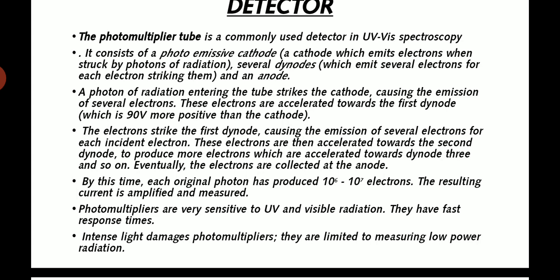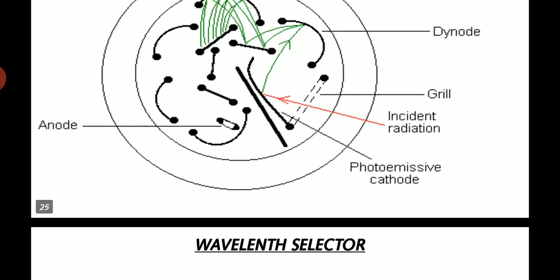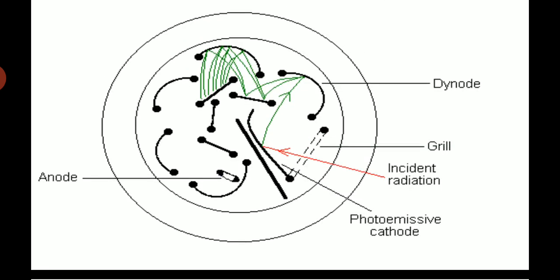Detector. The photomultiplier tube is commonly used in UV visible spectroscopy. It consists of a photoemissive cathode, a cathode which emits electrons when struck by photons of radiation, and several dynodes. A photon of radiation entering the tube strikes the cathode, causing the emission of several electrons into a dynode chain which amplifies more than the cathode. Photomultiplier tubes are very sensitive to UV and visible radiation. By this time the original photon has produced 10 to the power 6 to 7 electrons. The resulting current is amplified and measured.